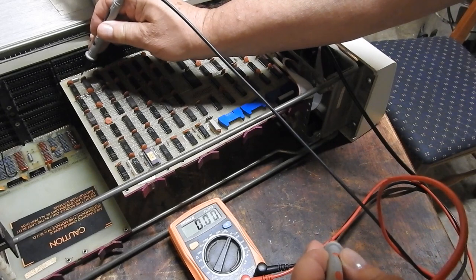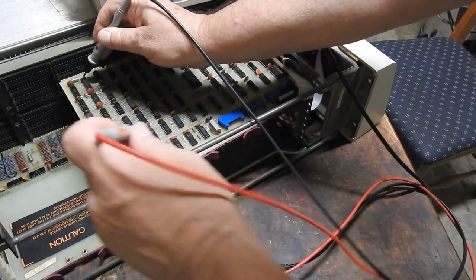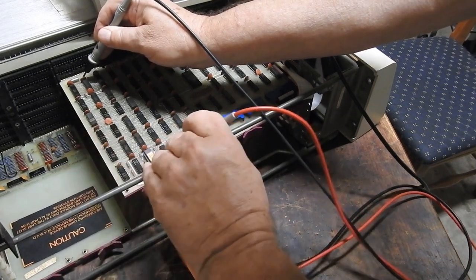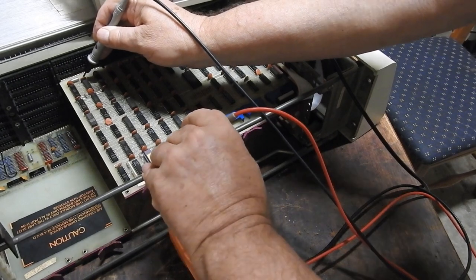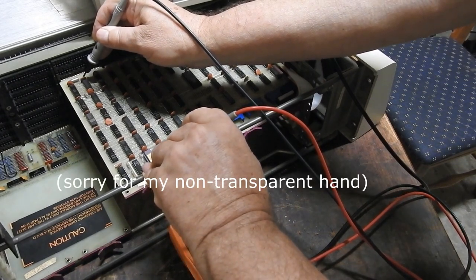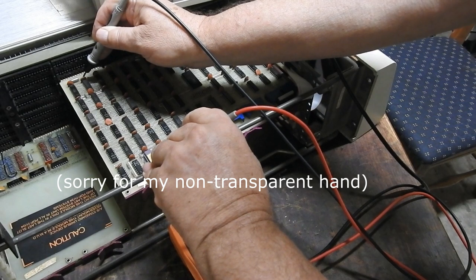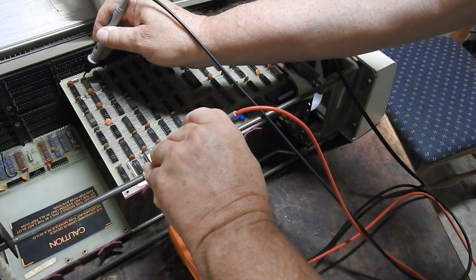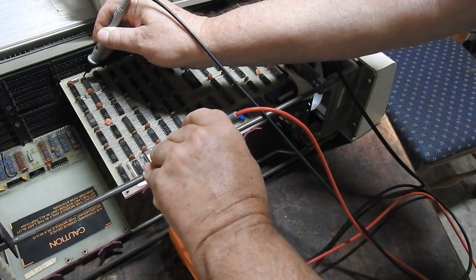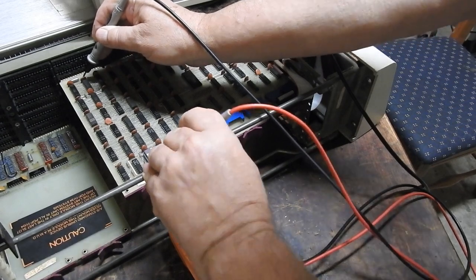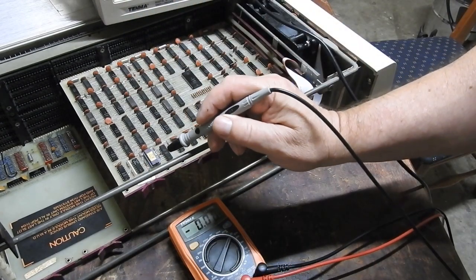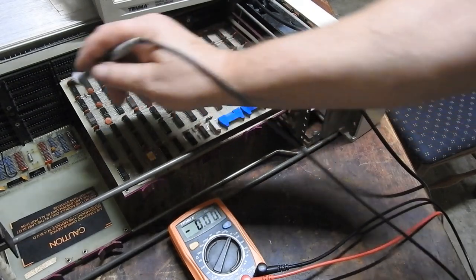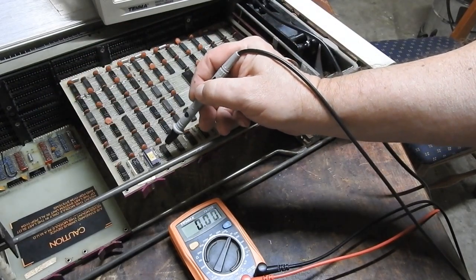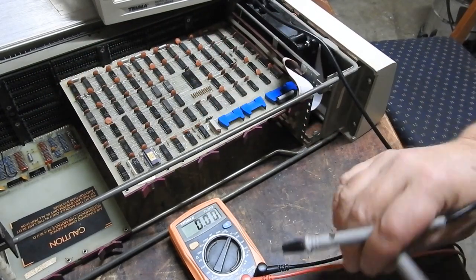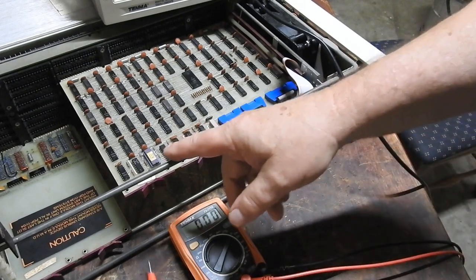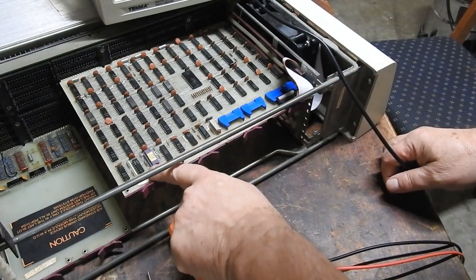I'll use that as a ground. Pin 1. Minus 8.7, a touch low, but probably good enough. The manual actually says 9 volts, but it's minus 9, which comes from the minus 15 volt supply via these two Zener diodes here. Right, the next thing to check is for 1 megahertz clock on that test point there.